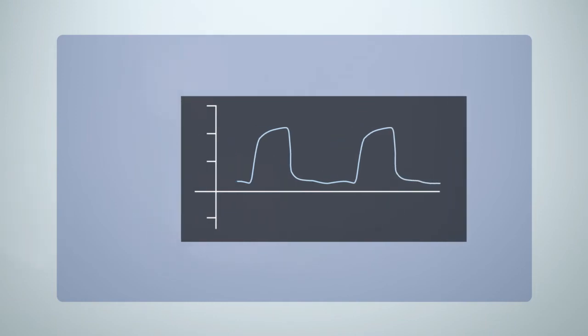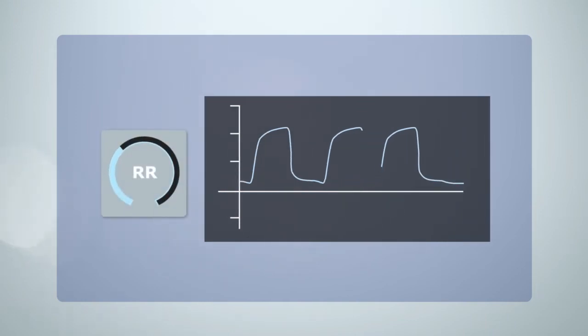This pulse enables the delivery of breaths for each patient to be dynamically controlled. Increasing the rate will increase the number of breaths. Increasing the inspiratory time of each pulse will result in longer breaths.